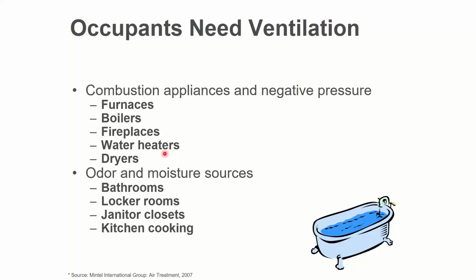We'd like to take it directly from outdoors and bring it directly to the appliance. But if we don't do that, the appliance will just have louvers on the front of its door, sucking air in from your space. If it does that, I have to bring more air into the space to compensate. Either way, anything burning a fuel will have an exhaust pipe, and if that pipe is sucking air out, something else has to bring combustion air in.